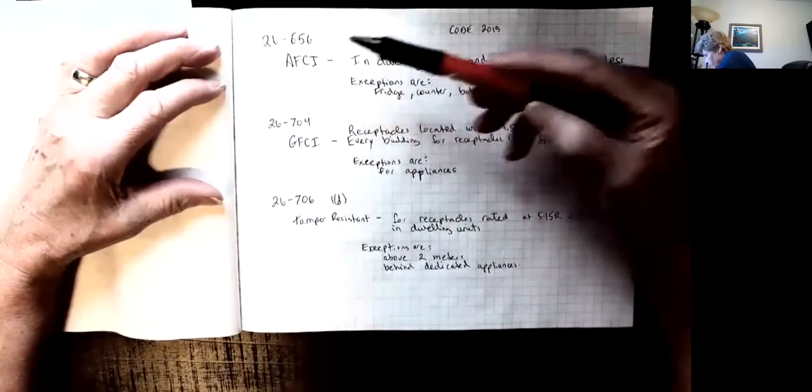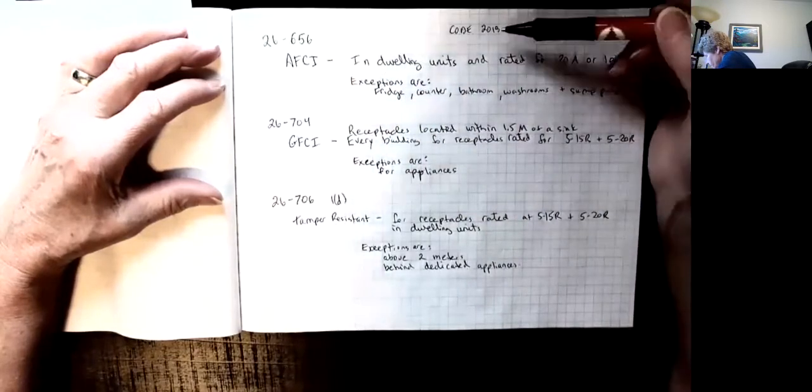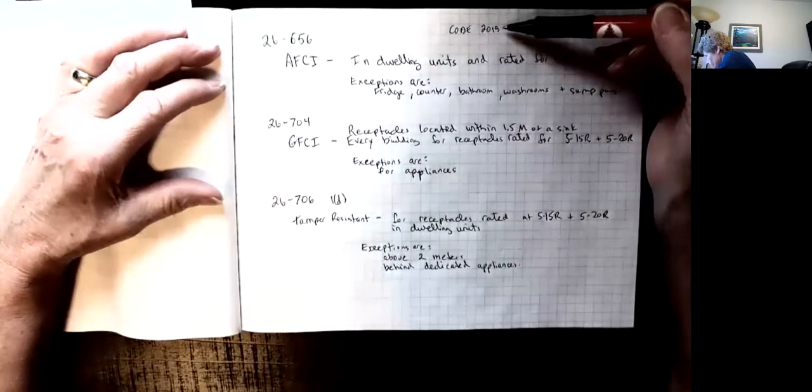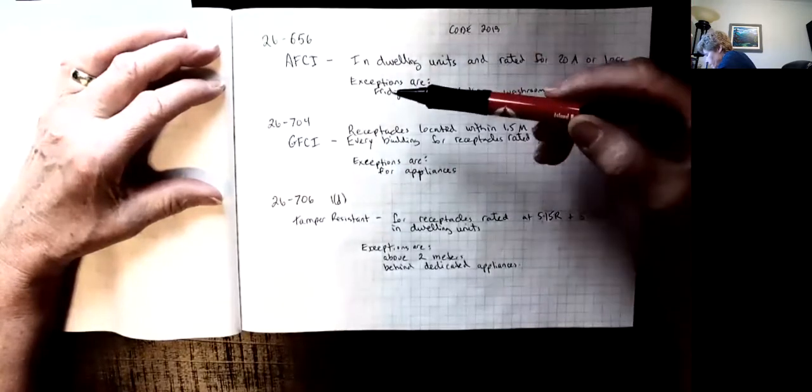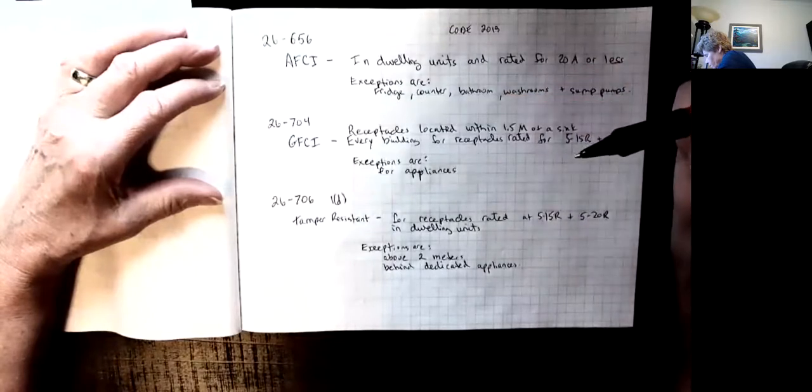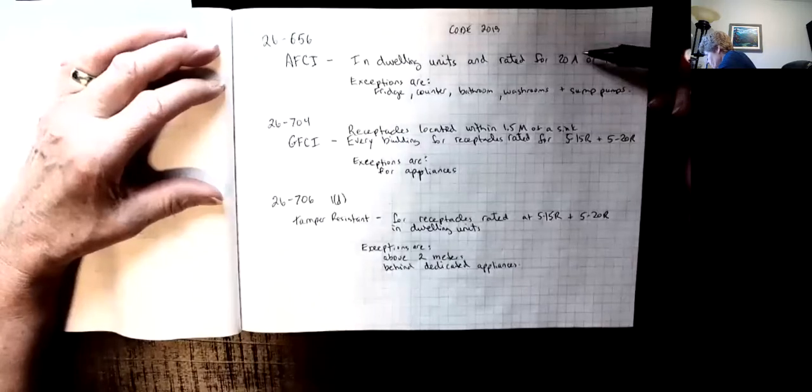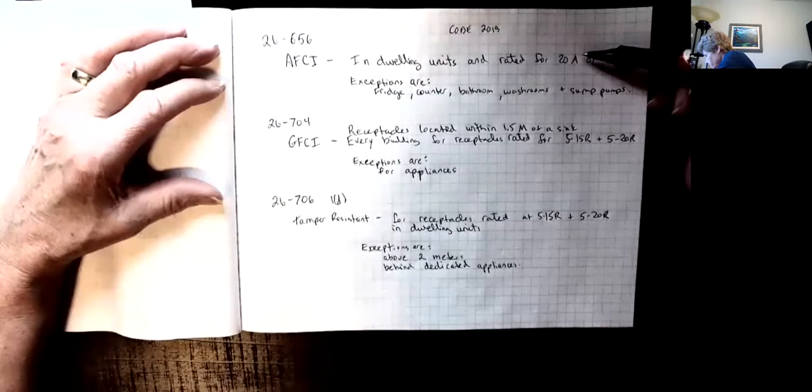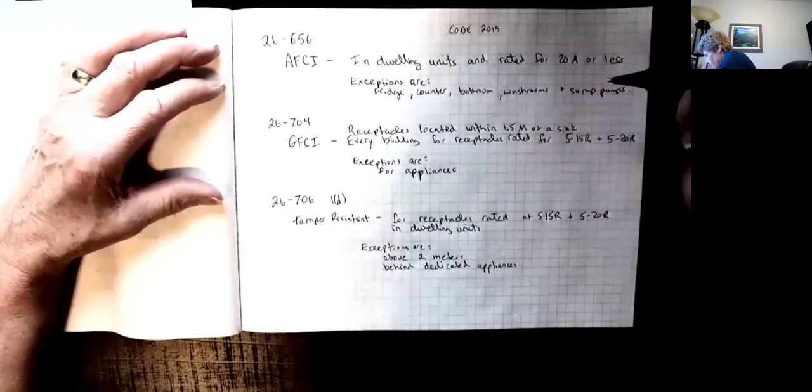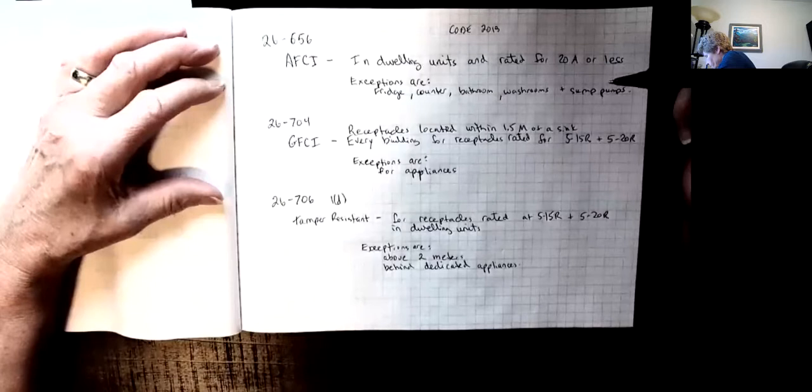One is 26656. Of course this comes out of the Canadian Electrical Code 2018. It's regarding the AFCIs or arc fault circuit interrupters and this applies to receptacles that are rated for 20 amps or less. Every receptacle except for these exceptions have to be protected by an AFCI and the exceptions are the fridge, counter plugs, bathroom or washroom plugs and sump pump plugs.